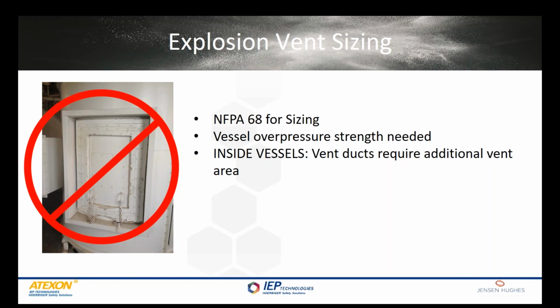And you also have to follow the NFPA calculations to determine what the overpressure effects are of having that vent duct. By placing a vent duct that's longer than the hydraulic diameter of the vent opening, you're going to see back pressure. And the longer the vent duct is, the more the back pressure is going to be, which means that you're either going to have to oversize the vent to accommodate for that back pressure, or you're going to have to beef up the vessel to compensate for that back pressure.